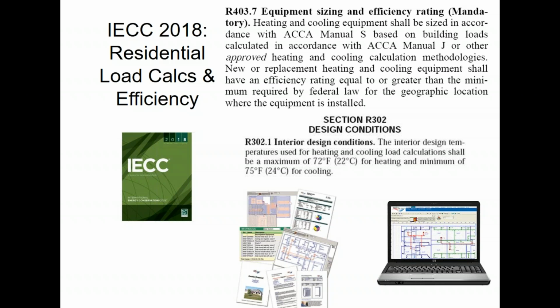As part of this discussion, the Energy Code requires you to not heat the structure, or at least not design the structure to be heated, above 72 degrees. If your customer says, I want to heat it to 75, you're not allowed to design it that way by code. And you're not allowed to design it to cool below 75. So if your customer says, man, I really want to hang meat in here, I want it to be like 67 degrees in here all the time, you're not allowed to legally design that. 75 is what you have to design for as a low end on the cooling side. You can make it higher than 75, but you probably wouldn't. So that kind of goes along with those set points.